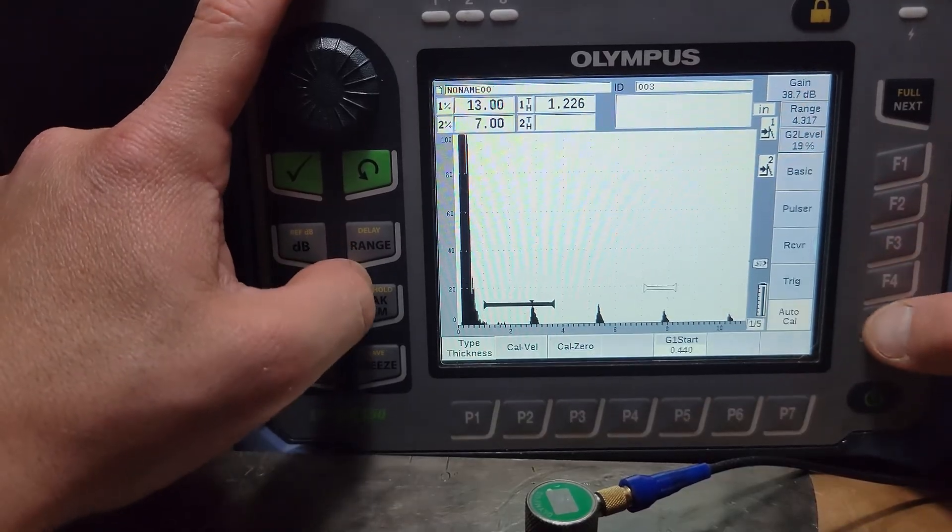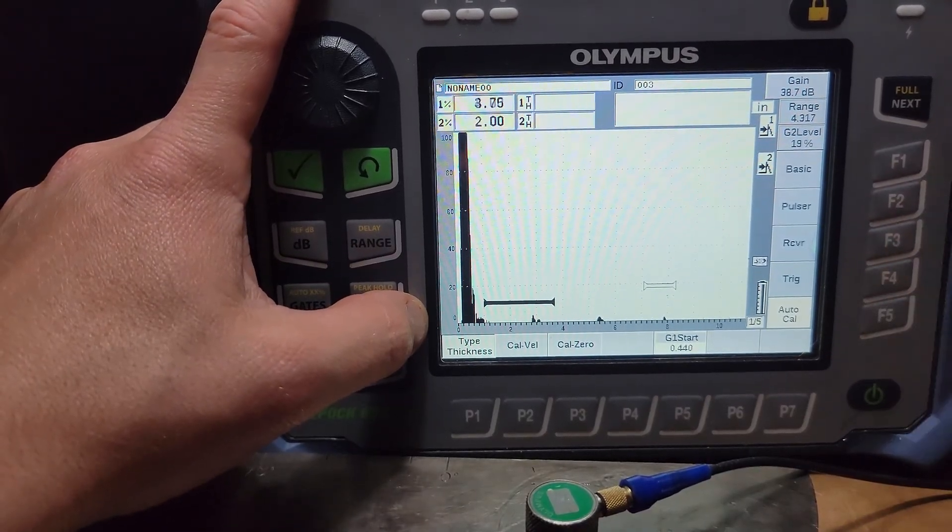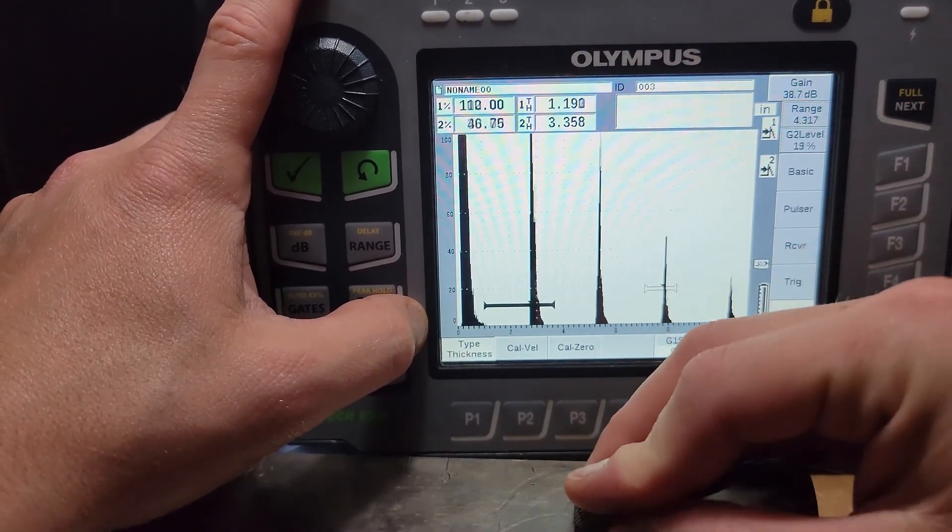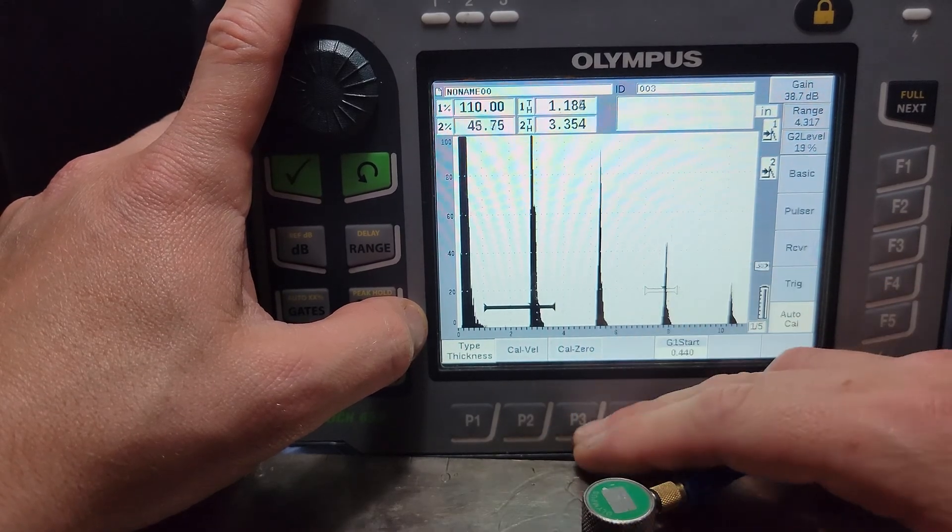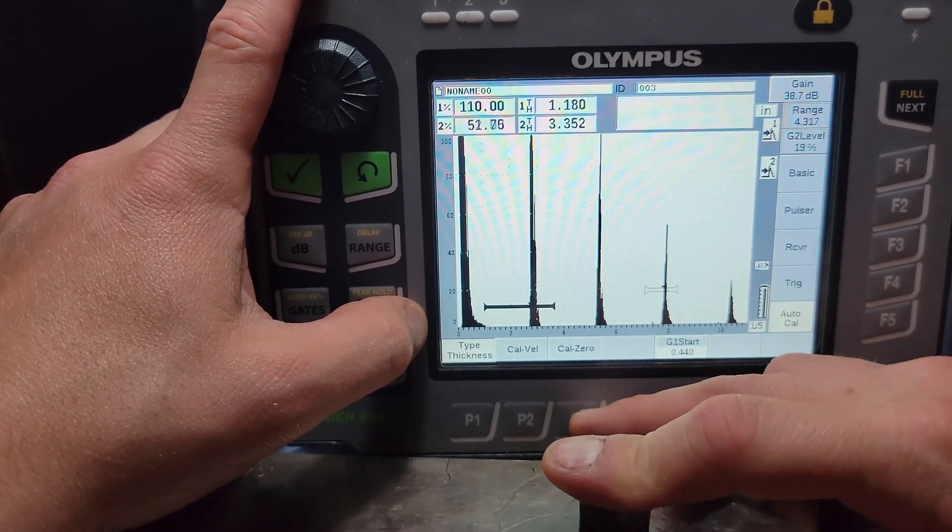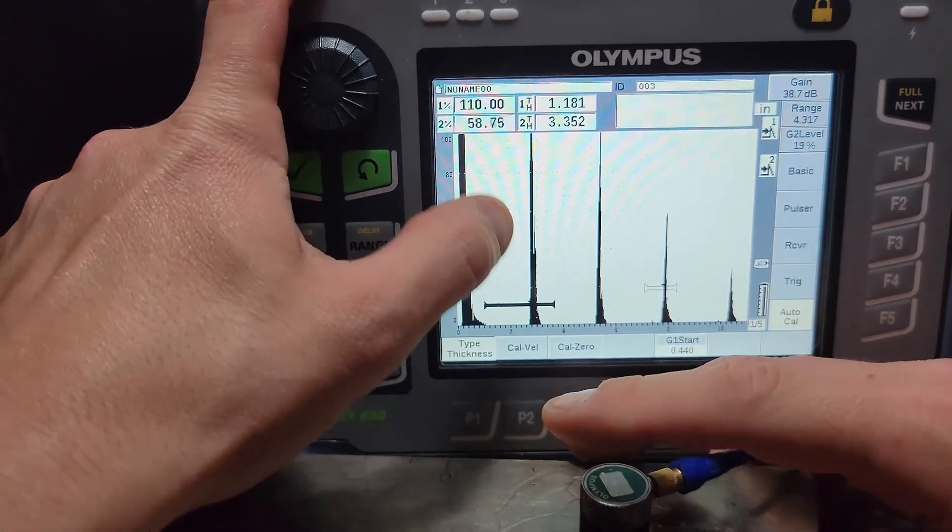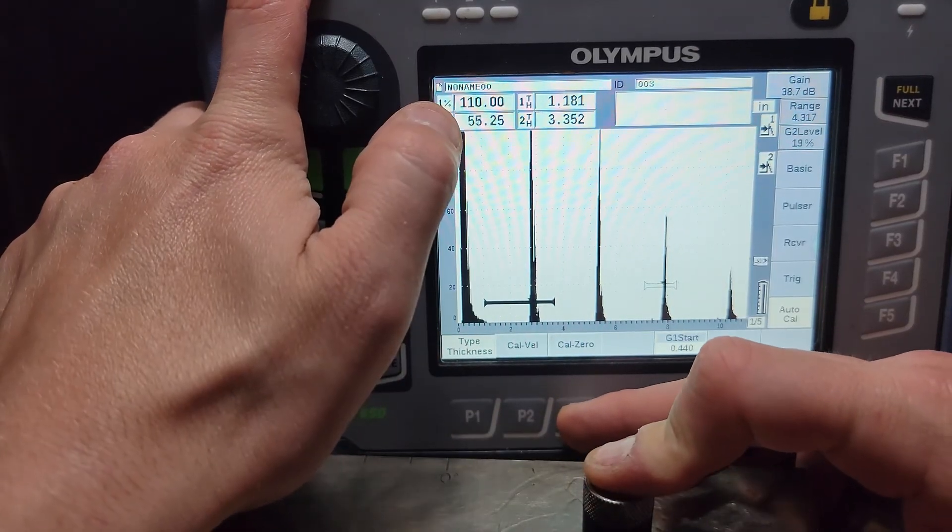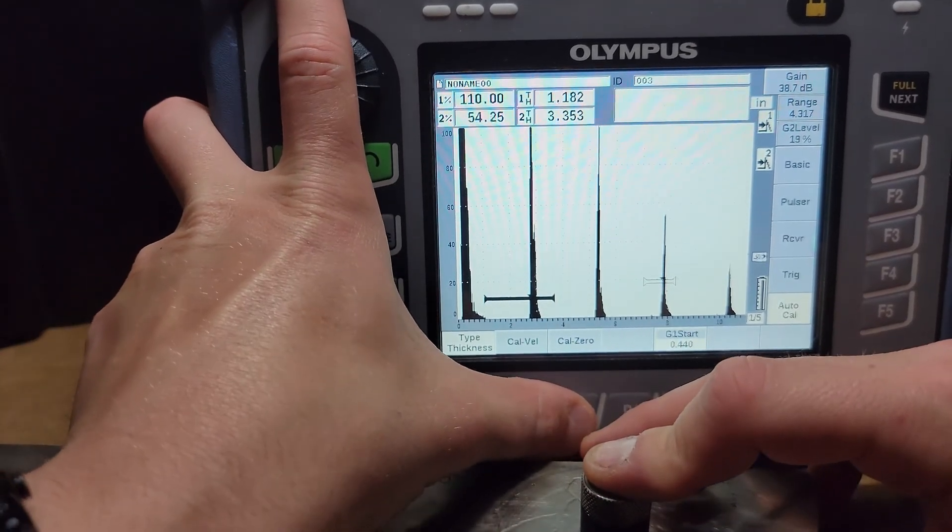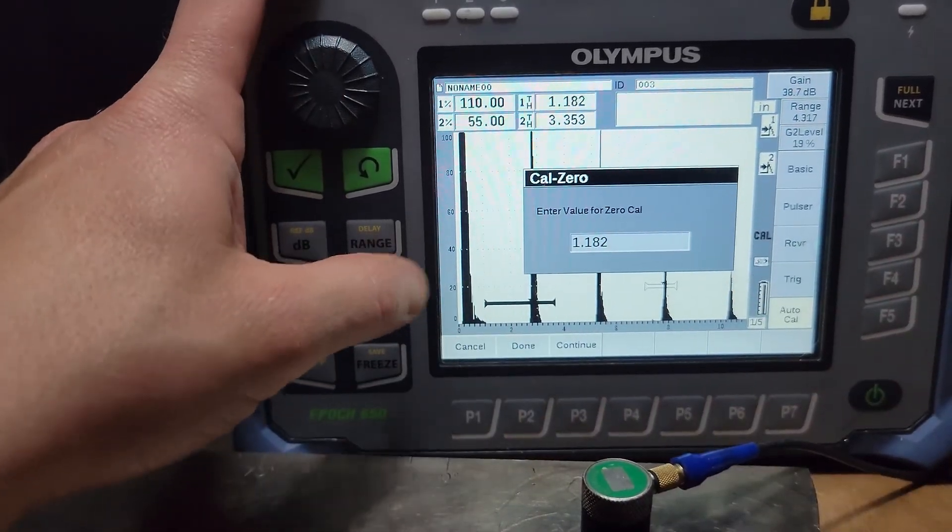But I know that this reference standard here is one inch thick, right? Into the auto-cal, let's produce a reflector from our one inch thickness. Begin with cal zero from a zero point. Oh, I can't. From cal zero. Boom. That's going to be our zero point.